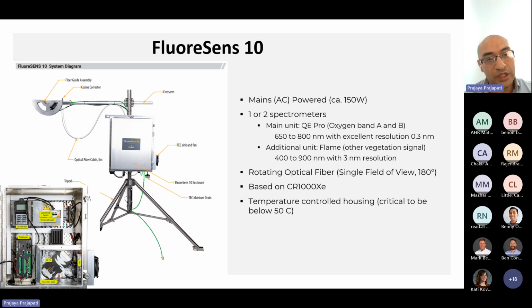It's based on a data logger and also on a fiber guide assembly that rotates up and down. And the enclosure where the spectrometer is placed is temperature controlled so that the internal TEC of the spectrometer can maintain the internal temperature of the spectrometer at -9 degrees centigrade. And this is required for reducing the thermal noise.